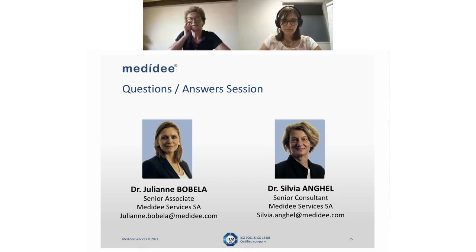Shall we all conduct PMPF studies, or when to conduct PMPF studies? Can you explain a bit this? Yes, it is a requirement as a part of the IVDR to perform PMPF activities after having placed your device on the market. Now, these PMPF activities can, if duly justified, be waived, but you really need to justify it.